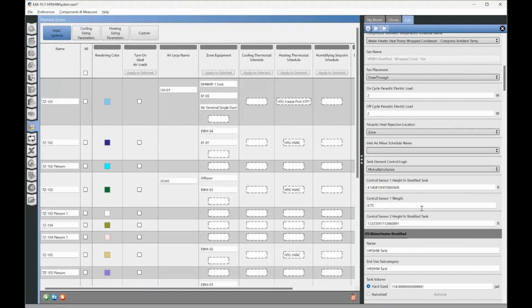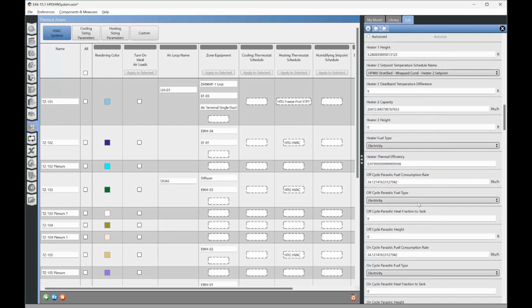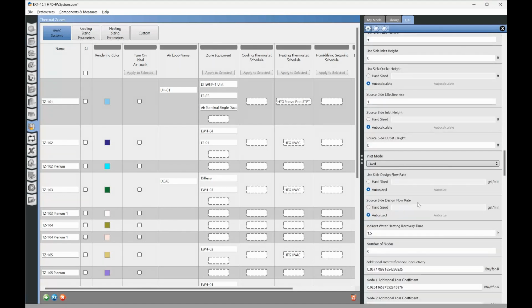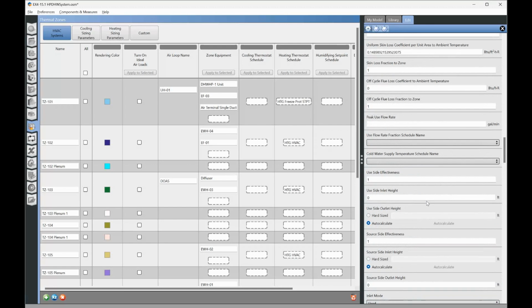If there are 2 control sensors in the tank, there might be some optimization that goes on, and then you can add a control sensor weighting. I believe this weights control sensor 1, so it puts higher priority on the sensor at the top of the tank versus the sensor at the bottom. If you're averaging these 2 temperatures, it gives more weighting to the sensor at the top of the tank. So that's it for our heat pump water heater input, and we'll go ahead and run the simulation and see how that turns out.